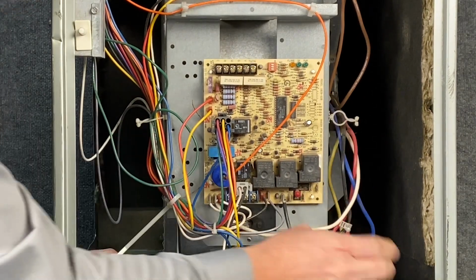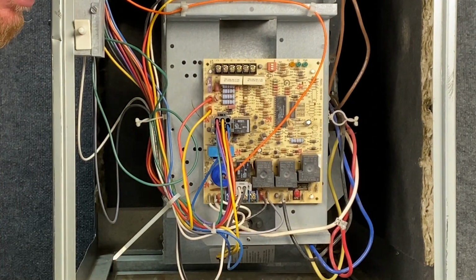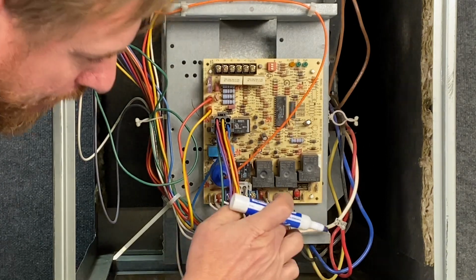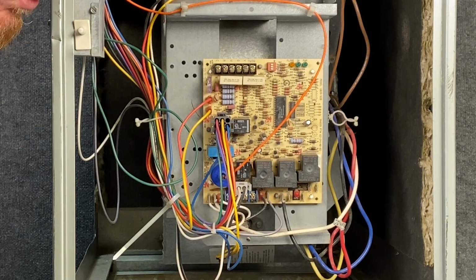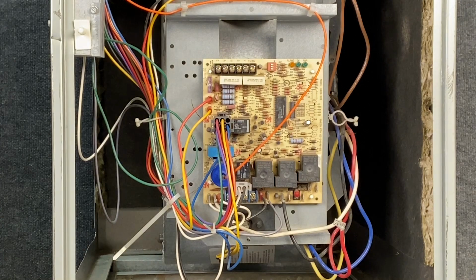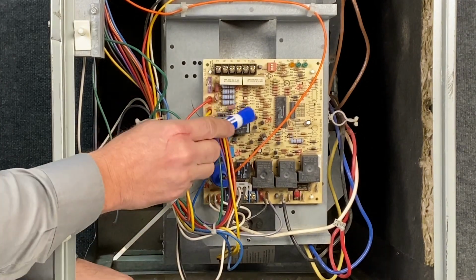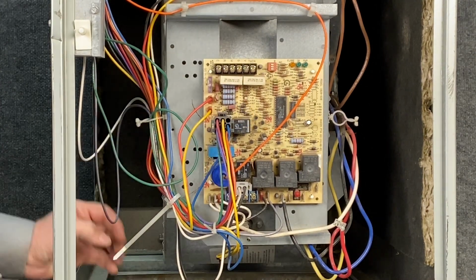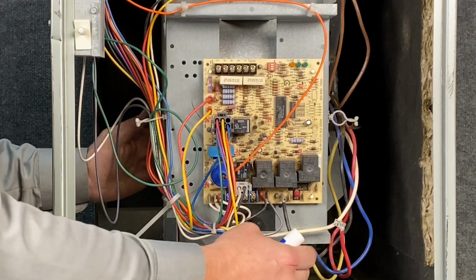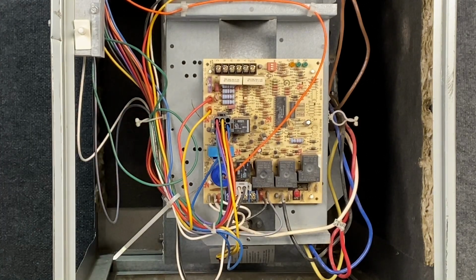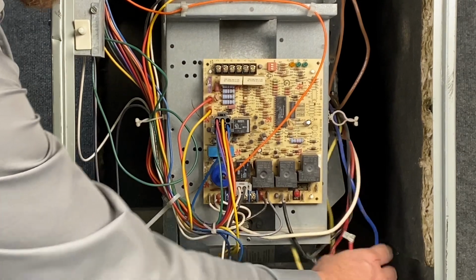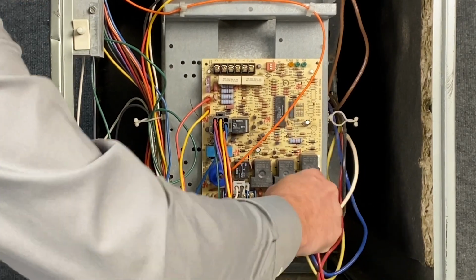and now we have this black wire left. So I'm going to write down in my notes, black, and that wire goes to the terminal, says cool. What that really means is when the thermostat has a call for cooling, the control board reads that through the Y terminal, and it puts the blower in the highest speed. Black is high speed. We're moving the most amount of air into that house. So if we move those wires, we see that we still have, oh, I didn't even unplug it.